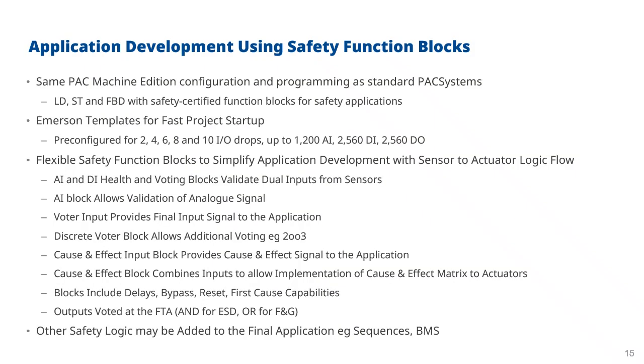So hardware is one aspect. The other area where Emerson has done a lot of work is in supporting application development using safety function blocks. Now, it's the same PAC Machine Edition configuration programming and software as standard PAC systems. So you can use ladder logic, you can use structured text, you can use function block diagram. But what we've added is a variety of safety certified function blocks specifically intended for safety applications. And along with that, we have Emerson templates which allow you to have fast project startup.